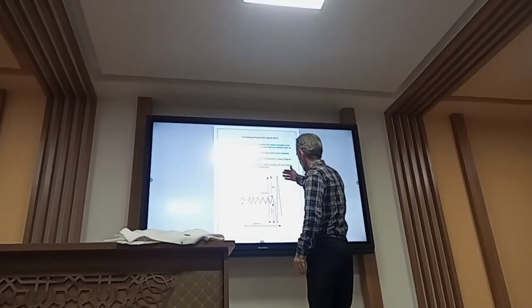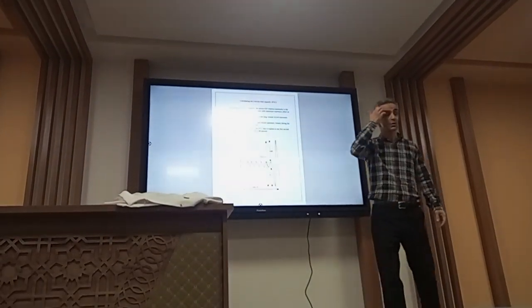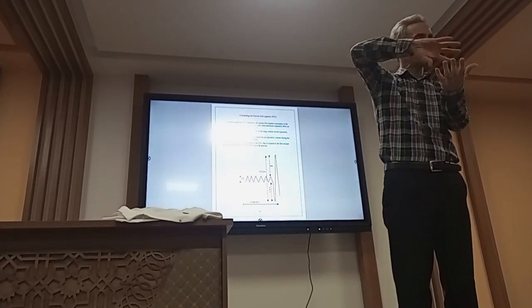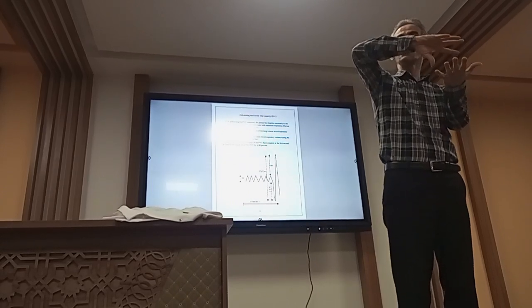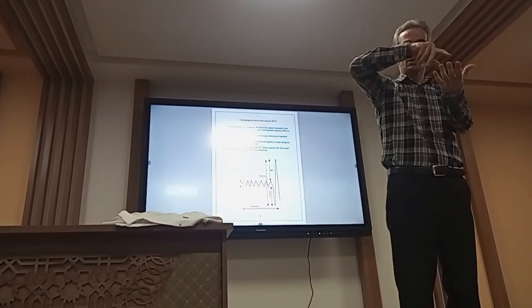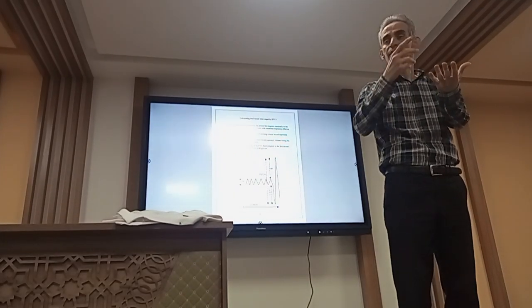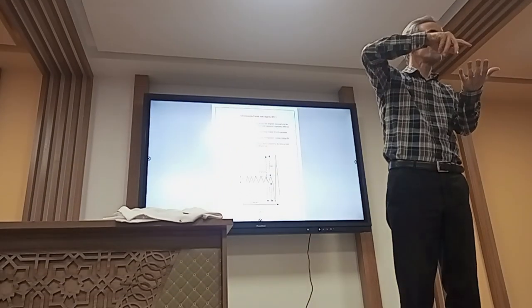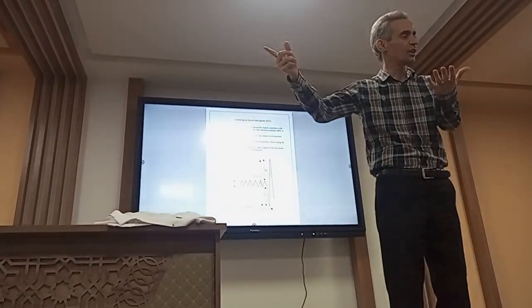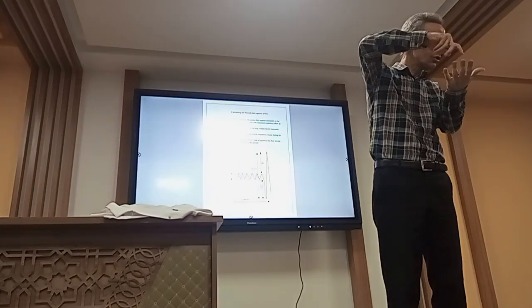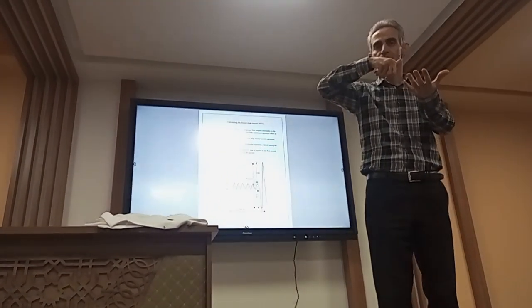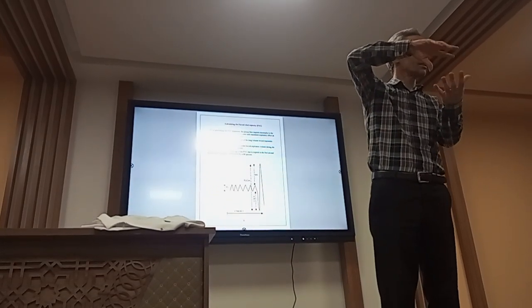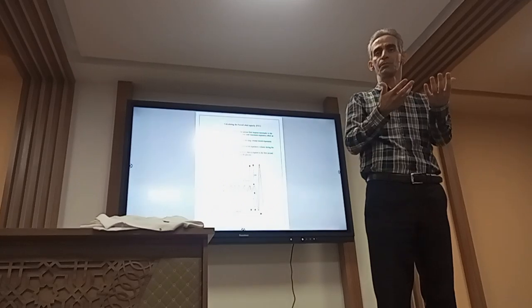For example, you can see here, you should know that the recording drum or cylinder has a rotation. And this rotation speed can be regulated by us. It's better we set this rotation speed on 2 centimeter per each second. This rotated cylinder can record the spirogram.